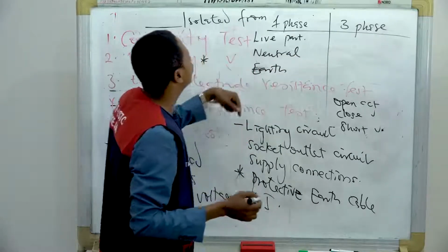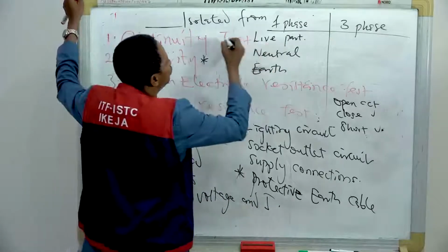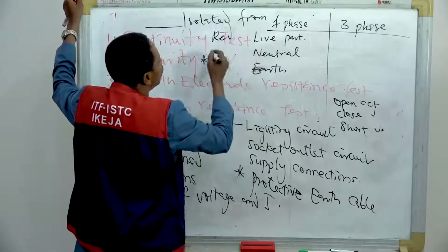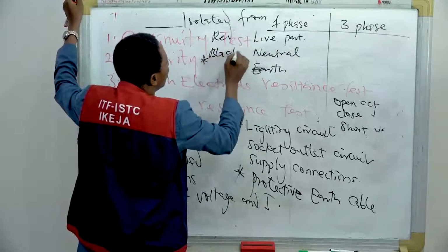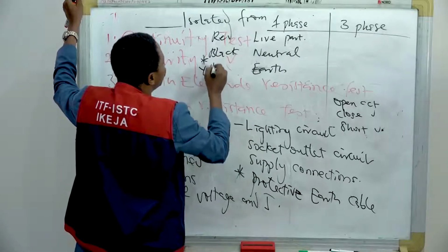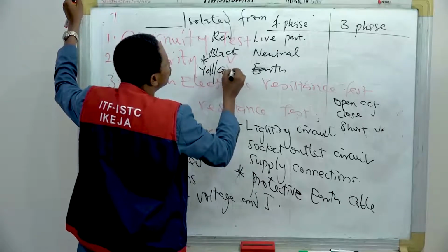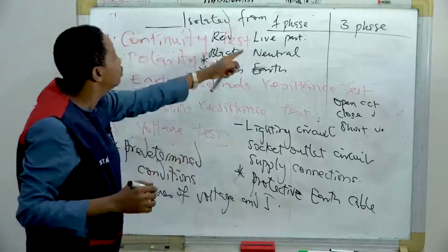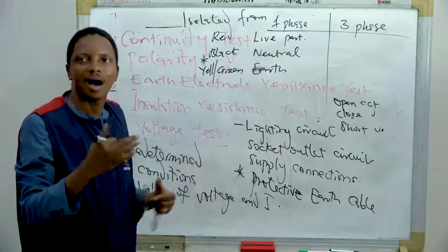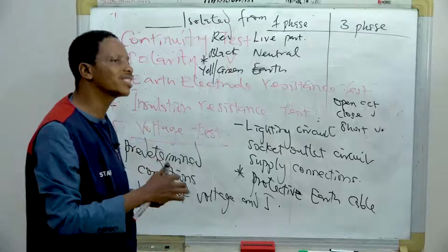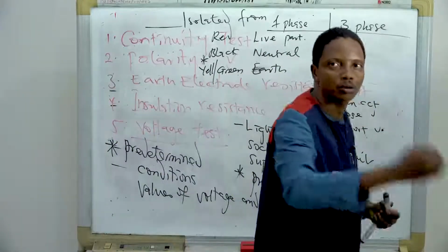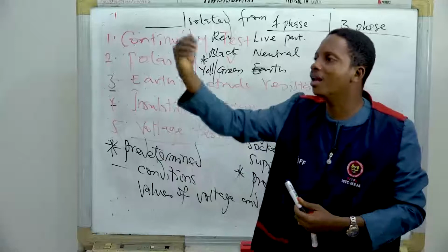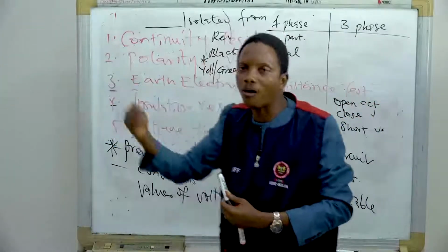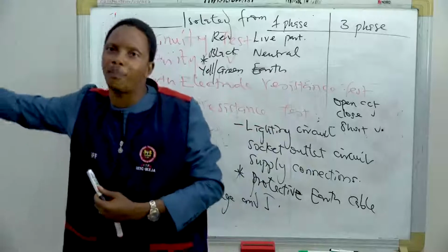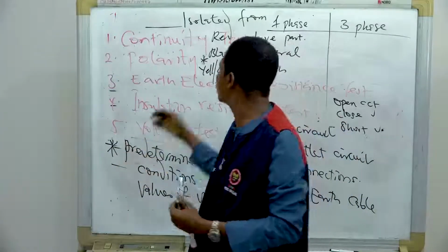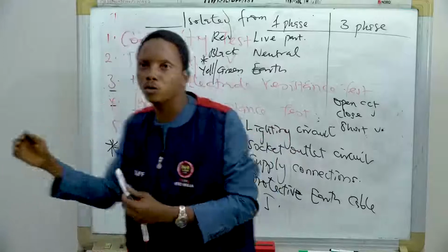And most of the time, they come in color. Live, red; neutral, black; earth, yellow stroke green. So, we want to confirm your polarity. Are they uniform? Constant connection of live to live parts. Constant connection of neutral to neutral parts. Constant connection of what? Earth to earth parts. So, you must not miss it.